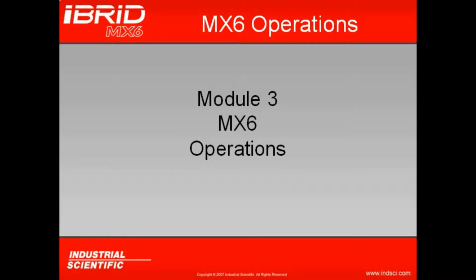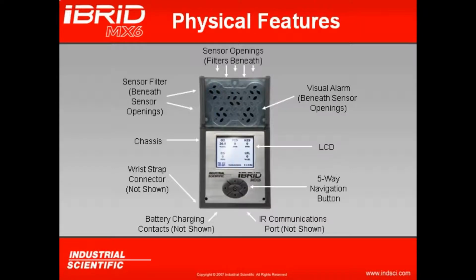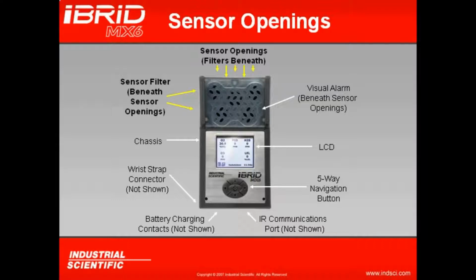In Module 3, we're going to cover the MX6 operations. Let's start by taking a tour of the physical features of the MX6. At the top of the instrument, underneath those openings, is where your sensors are located. We have to ensure that we keep this area free and clear of obstructions. This is the only place that the instrument will see gas. Therefore, we have to keep these areas free of obstructions.